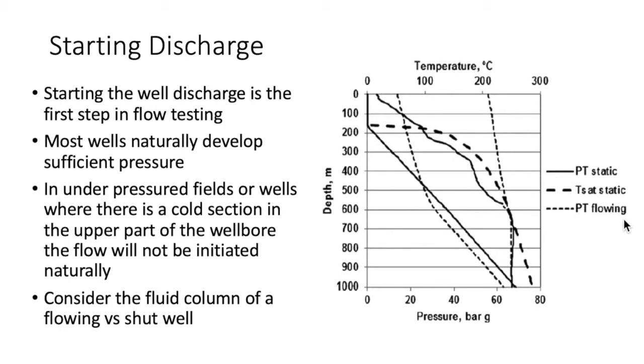The first step in flow testing is to initiate well discharge. This is not usually difficult because most geothermal wells naturally develop sufficient pressure to begin discharge as soon as the well surface is drilled and the wellhead is opened. However, some wells do not have enough pressure, or have cold water at the top of the water column that prevents boiling and sufficient pressure buildup. If a well does not spontaneously discharge after drilling, the fluid will have to be boiled or cool water replaced with hot water to initiate discharge.